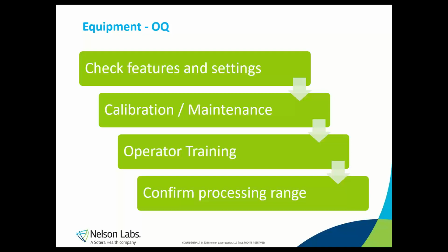And this is where you would want to write up a calibration and maintenance schedule for the equipment to make sure that it is checked for continuing compliance and given the periodic attention that it needs to keep performing as expected. The operator training is also documented in the OQ, and it's a good time to develop some kind of standardized training for future operators.